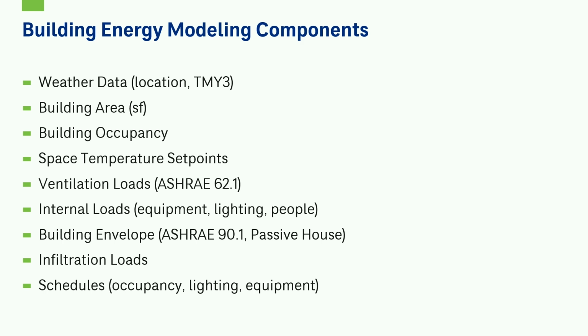Ventilation air, ASHRAE 62.1 specifies these requirements. We need to bring outdoor air into the space, which is unconditioned, and then you need to condition it to maintain your space temperature, which adds to your heating or cooling loads. There are also internal loads: electrical equipment in the space, your lighting, and people in the building radiating heat into the space, which could decrease your heating loads or increase your cooling loads.